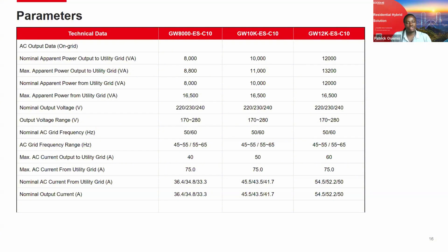It's able to output 10% additional power during, let me say, ideal conditions when the inverter temperatures are low. The inverter is able to do 10% more. So the 8 kilowatt can do 8.8, the 10 can do 11, and the 13 and the 12 can do 13.2 kilowatt. Output currents are high, so you can see 40 amps up to 60 amps. That's quite high in terms of power ratings.